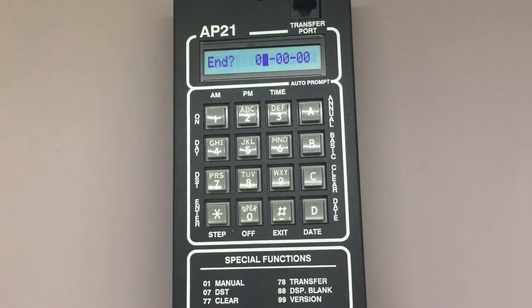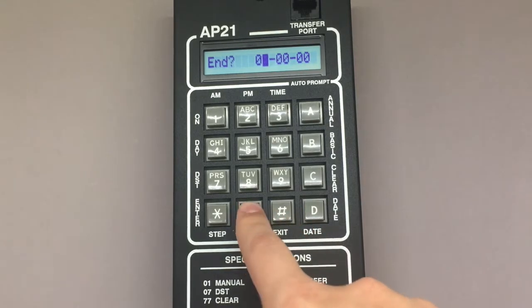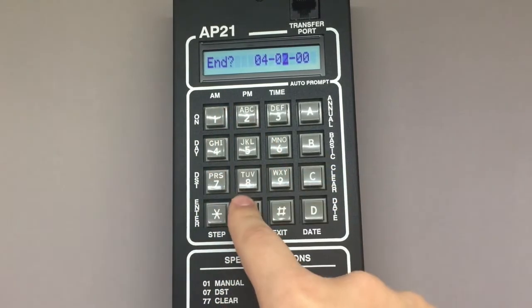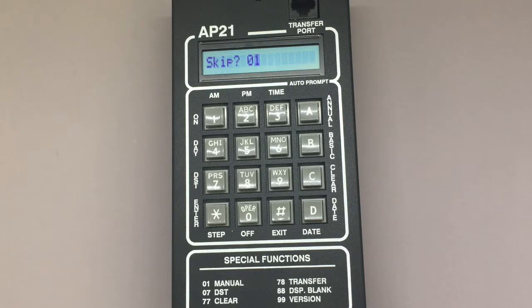This will take me to the End Date screen. If you're scheduling a skip plan that's just a one-day holiday, like Memorial Day for example, you'll just enter the same date that you entered for the start date. But since Spring Break is a full 5 days off from regular programming steps, I'm going to use the keypad to enter April 20th: 04 star, 20 star, 18 star. This completes the programming for the first skip plan and automatically takes you to the next plan number where you can input the dates for the rest of the skip dates. Remember that a skip plan overrules the previously programmed steps and replaces it on the scheduled days with no relay activity.